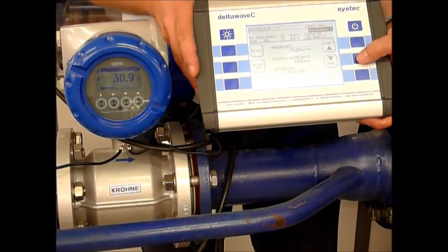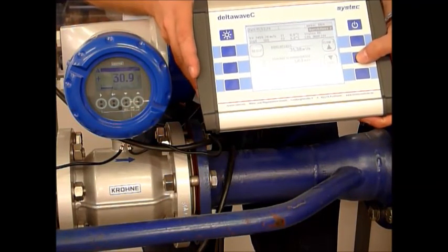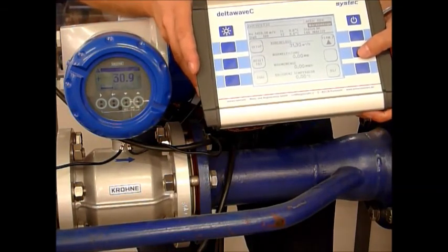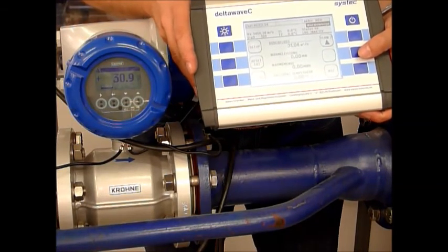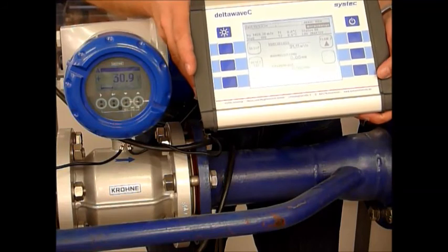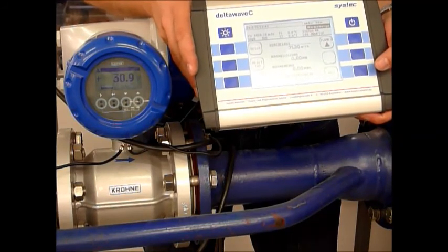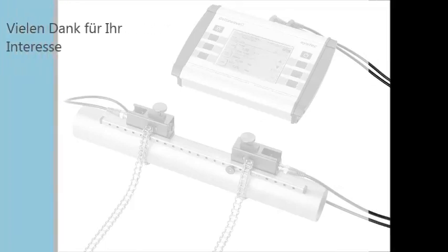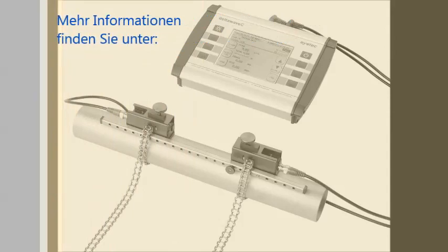And with this we have completely set up our flow meter. You can see here a very nice reading in comparison with the mag meter beside. Besides the flow, you can also measure heat by connecting two PT100s. You get diagnostic data like sonic velocity of the fluid. This was really easy and a fast task which can be done by everybody, also by you. Thank you for your interest. If you have any questions or requirements, do not hesitate to contact us. Thank you and bye-bye.